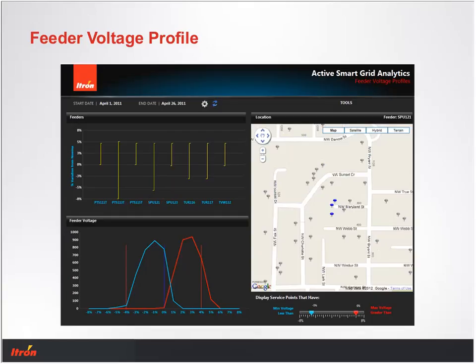I happen to know that this is all 3 services off of the same transformer. So immediately I suspect I may have an issue with the transformer, possibly, instead of a problem with the meters, but I need to validate that.